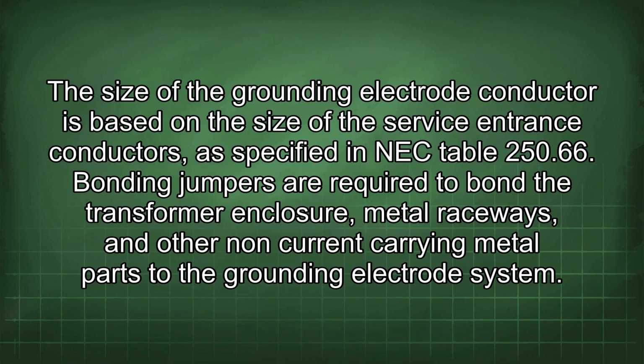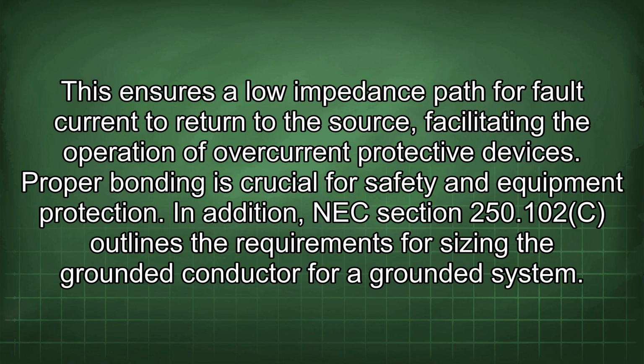250.66. Bonding jumpers are required to bond the transformer enclosure, metal raceways, and other non-current carrying metal parts to the grounding electrode system. This ensures a low impedance path for fault current to return to the source, facilitating the operation of overcurrent protective devices. Proper bonding is crucial for safety and equipment protection.